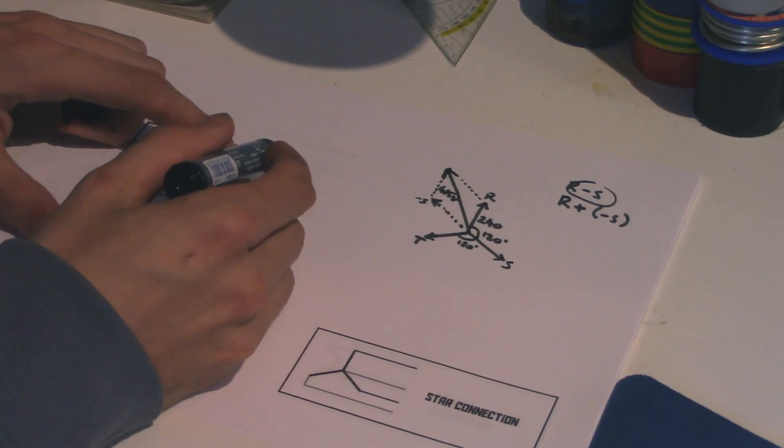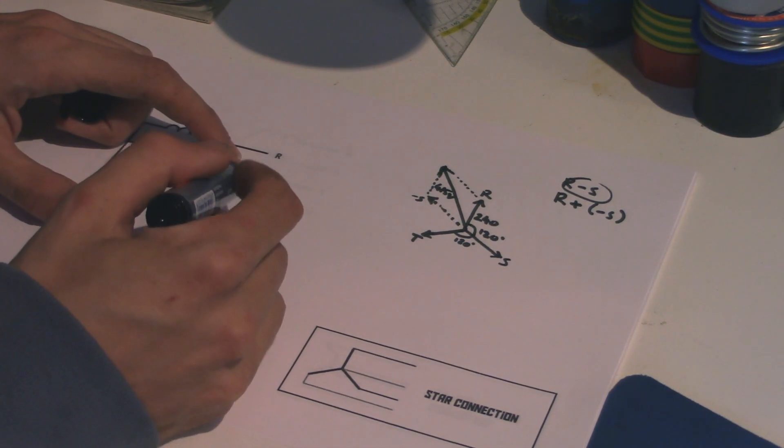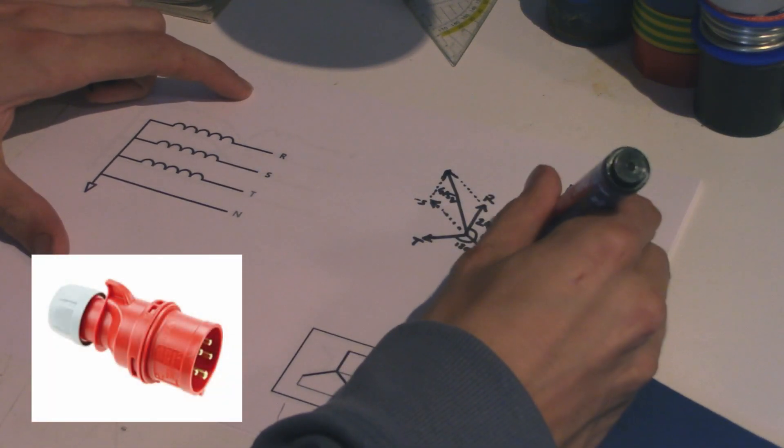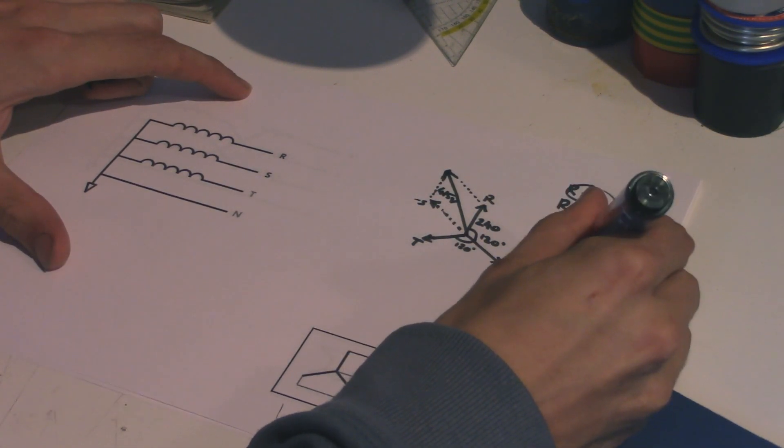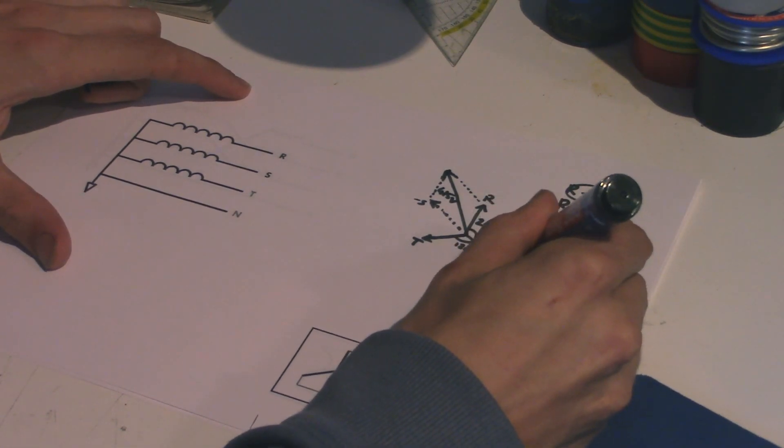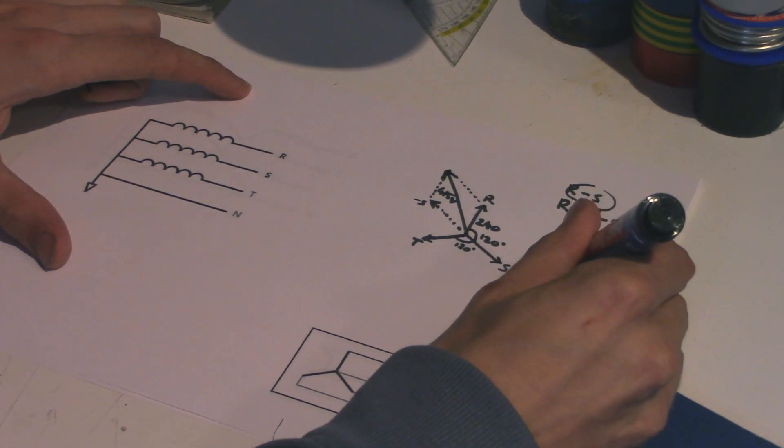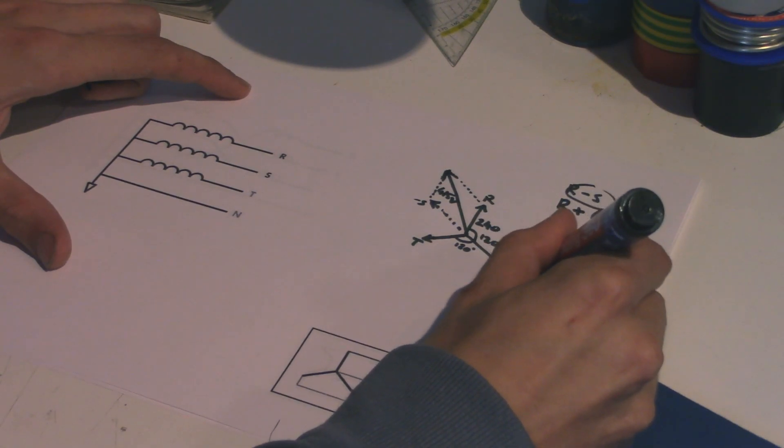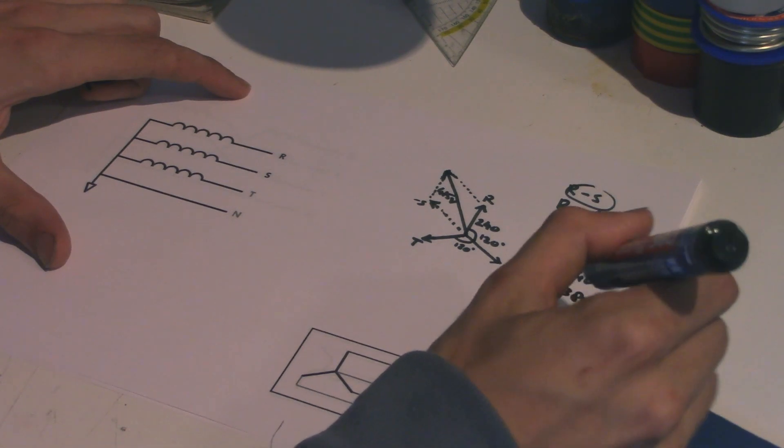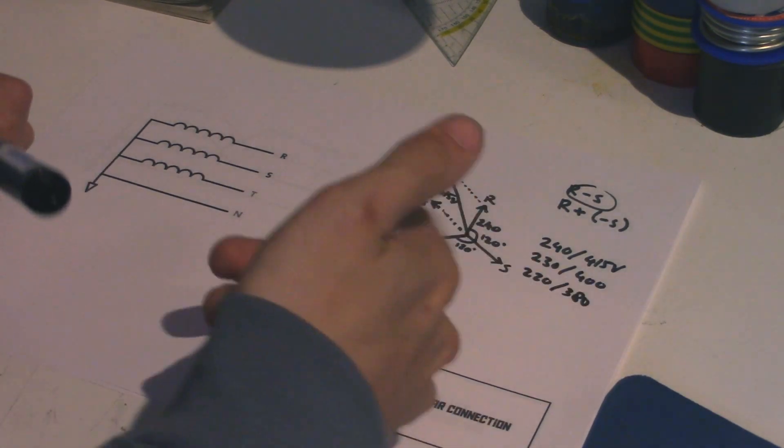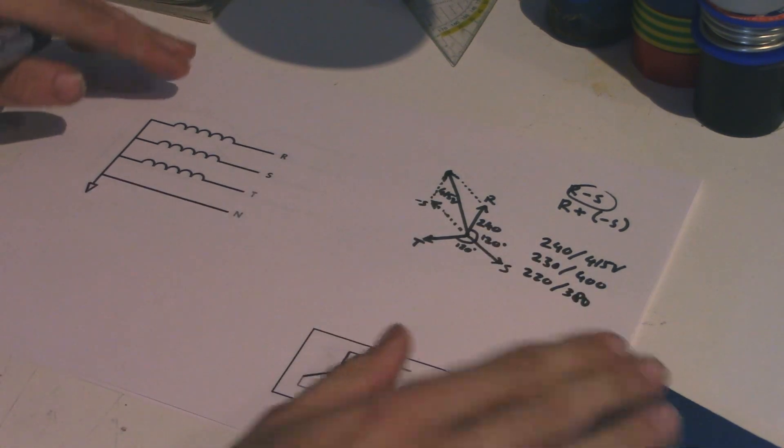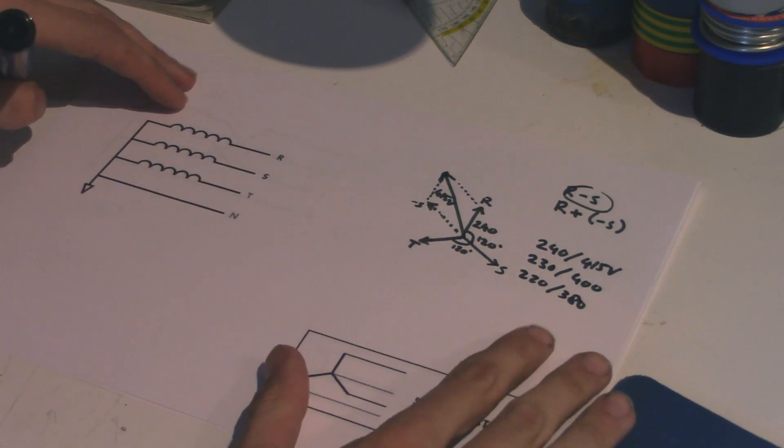And the same thing goes for the difference between R and T and T and S. So that's why on one of these big red three-phase power plugs, it says 240 slash 415 volts, or perhaps 230 slash 400 or 220 slash 380, if it's a bit of an older thing. But it comes down to the same thing. So that's our normal star connection at the output of the transformer.